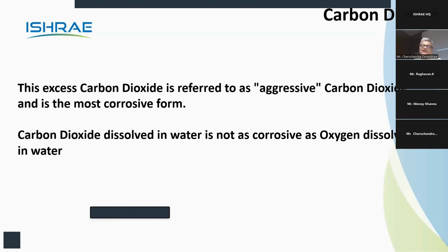Now that CO2 gets dissolved into water, like they have whatever formula Thums Up has. So that water is created containing Thums Up, and CO2 is injected from outside. That injection of CO2 is taking place at 3 degrees. At 3 degrees, the highest amount of CO2 goes into water in the minimum possible time. That is why 3 degrees is very important. So whenever they get the chance, they descale that heat exchanger. It's a plate type heat exchanger. One side is brine, or chilled water containing some amount of glycol, and the other side is Coca-Cola water or Thums Up water, and at 3 degrees CO2 is injected inside.